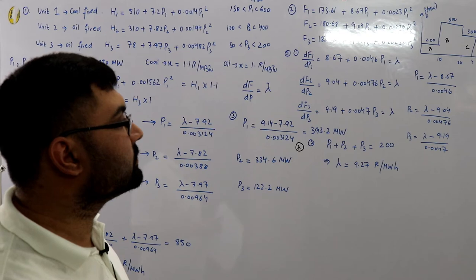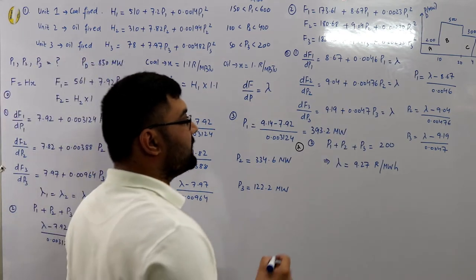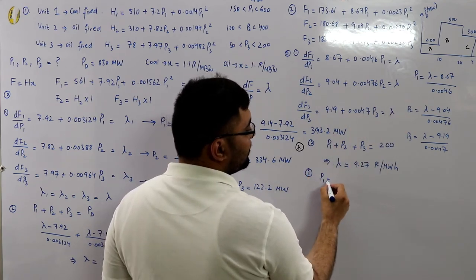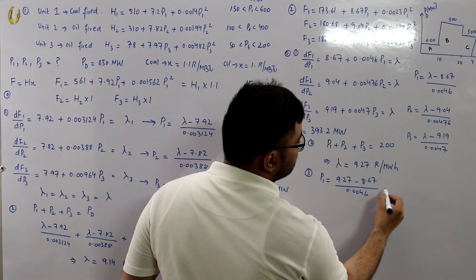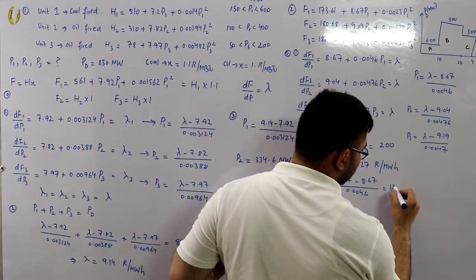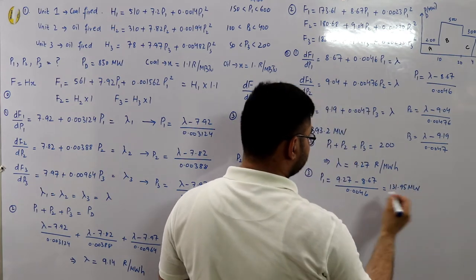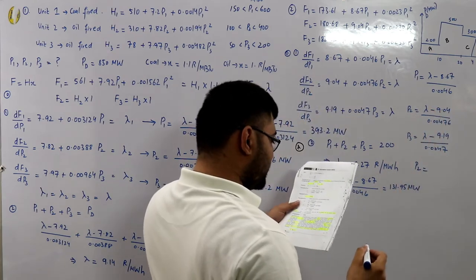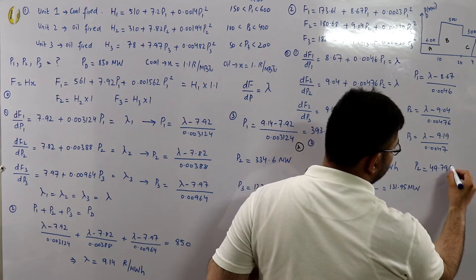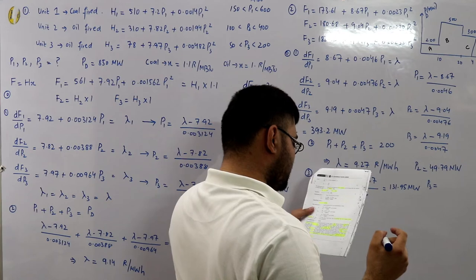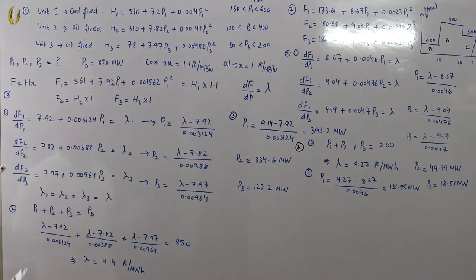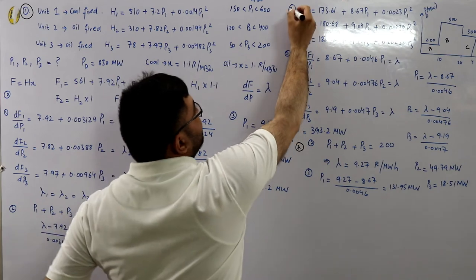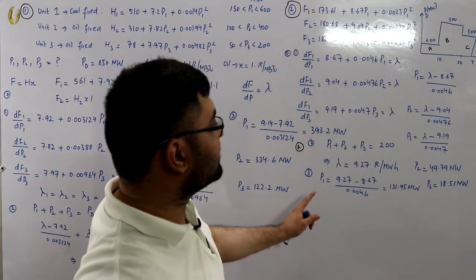Step number 3 for interval A: p1 = (9.27 − 8.67)/0.0046 = 131.95 MW, p2 = (9.27 − 9.04)/0.00476 = 49.79 MW, p3 = (9.27 − 9.19)/0.0047 = 18.51 MW. No economic limits to check. Summing: 131.95 + 49.79 + 18.51 ≈ 200 MW.